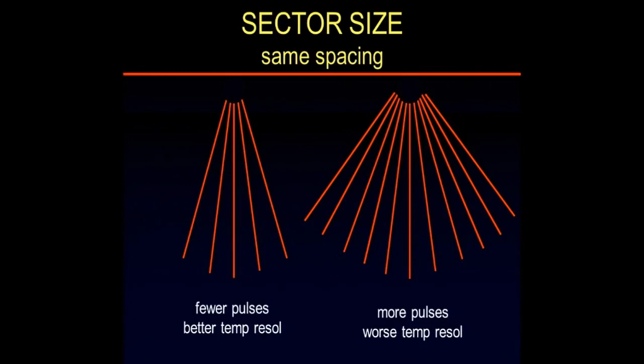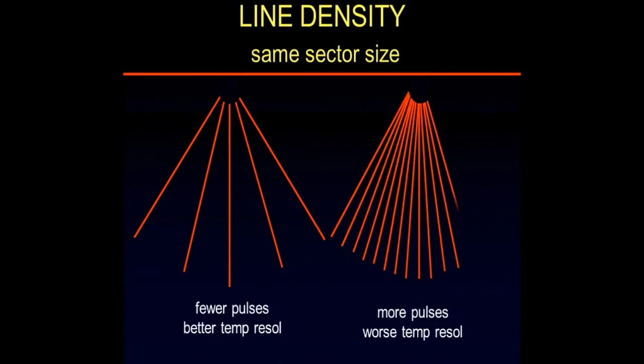So what happens when we change the line spacing? Well, if I have this, it doesn't take very long to make a picture. So my frame rate is high, but my detail is terrible. What about this? Here, my spatial resolution is excellent, but my frame rate is low. Now, we generally don't see this. This is set up in the presets because the manufacturers don't want us to do this, because they know that if we do this, we're going to blame them. So they hide this from us. But understand these four settings.